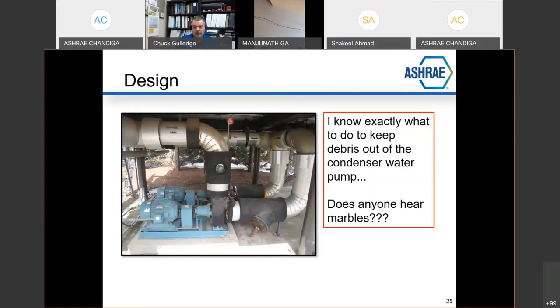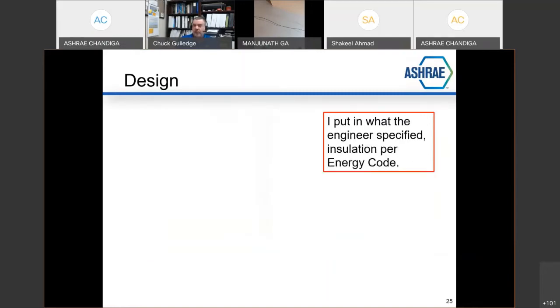What they didn't do was pay attention to where they put these strainers to protect these pumps, and the fact that these strainers actually clog up with the garbage that collects in these cooling towers. And you can see this was actually in North Carolina. So there's a lot of pine straw. There's a lot of debris that gets in the cooling tower. These started clogging up and the pumps started sounding like they had marbles in them, all because somebody put the strainers in the wrong location and didn't deal with capturing the crud in the cooling tower basin to start with. They destroyed some pump impellers.